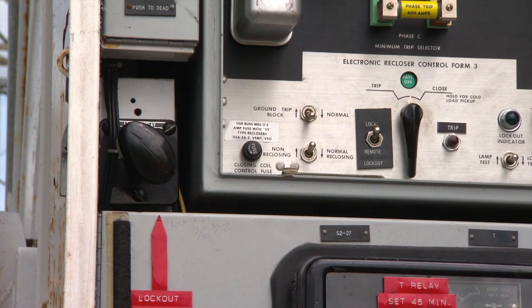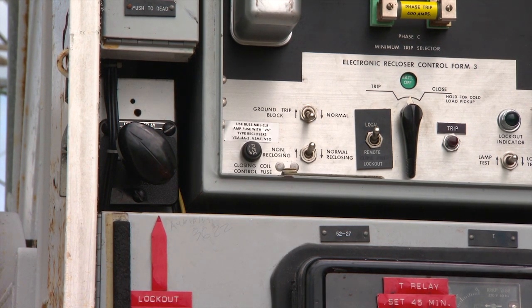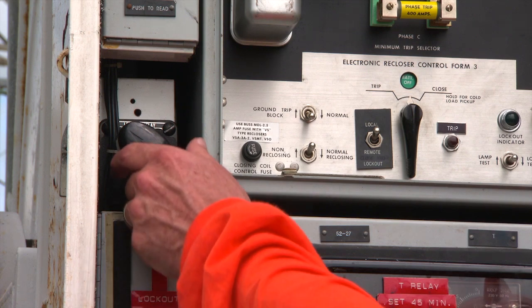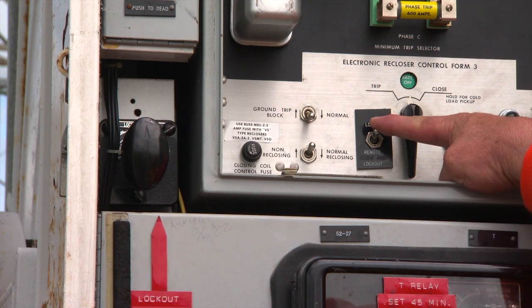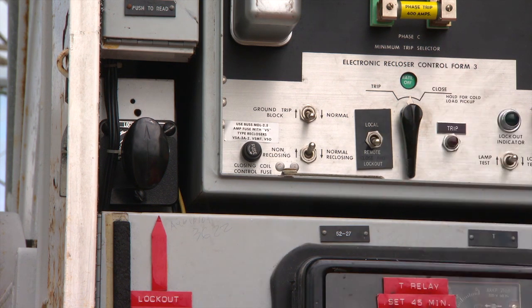Testing the 86 relay requires both reclosers in the closed position with the springs charged. Manually reset the relay and immediately place the recloser local remote switch in the remote position. After a small time delay of approximately 10 to 20 seconds, both reclosers should trip open. The 86 relay will trip the reclosers to protect the transformer in the event of loss of cooling.